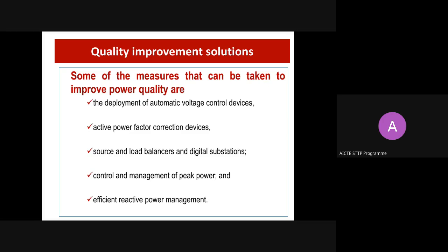Automatic voltage control devices, AVRs, we are placing at different locations to control the power quality. Active power factor correction: generally we place it at the load center, the customer premises, and after the load center at the distribution transformer level, then the feeder level, and then the substation level. These are the different locations where we place power factor correction. And then source and load balancing. We are balancing the voltage and balancing the supply with the demand.